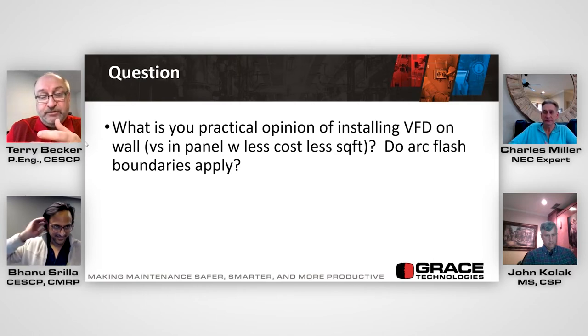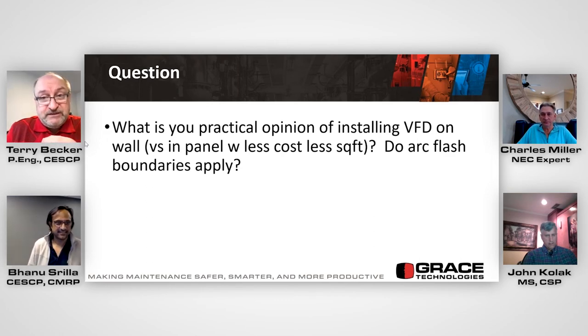We've got to temper this whole thing, use risk assessment - very powerful tool. And risk assessment is two things: potential severity of injury or damage to health, and likelihood of occurrence. We need to put more focus on likelihood of occurrence, but it is acceptable for unqualified persons that are authorized to go in front of electrical equipment, operate it, read HMIs.